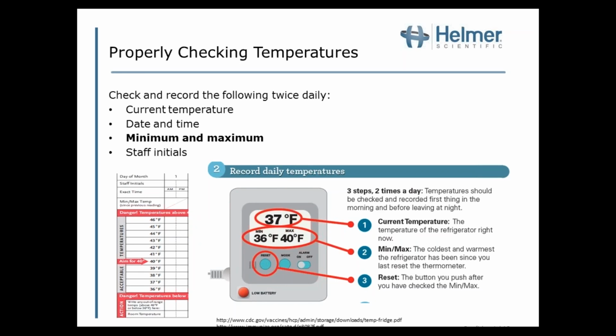Finally, after you check the min-max and the current and you log it, you want to reset the min-max so that the next time you go to check the temperatures, your min and max is only reflecting the period since you checked the last temperature.